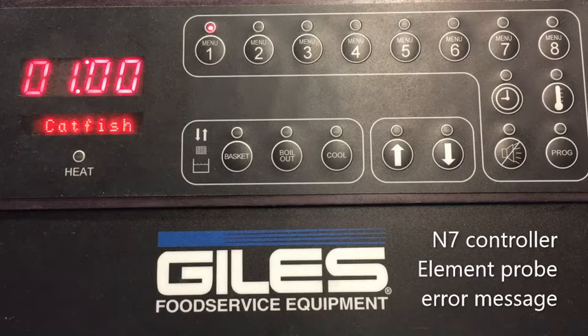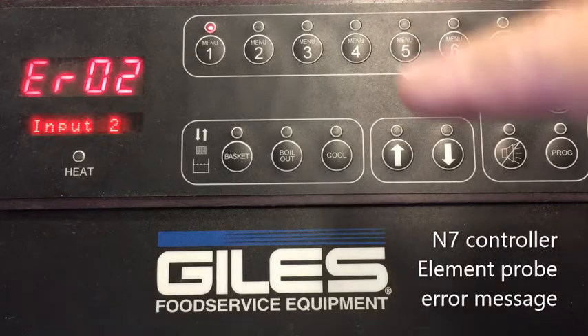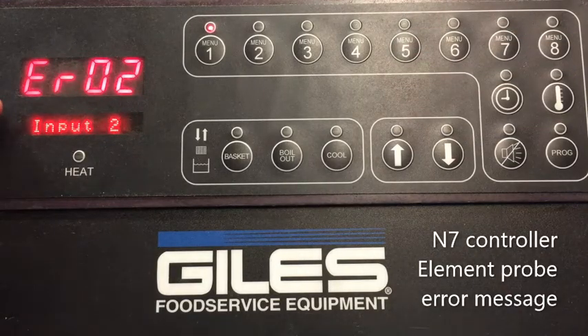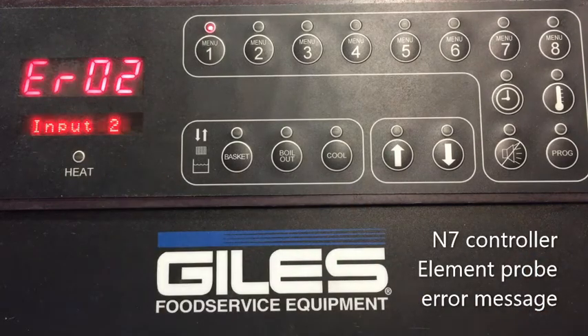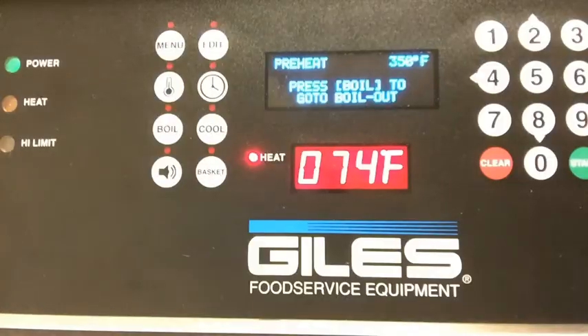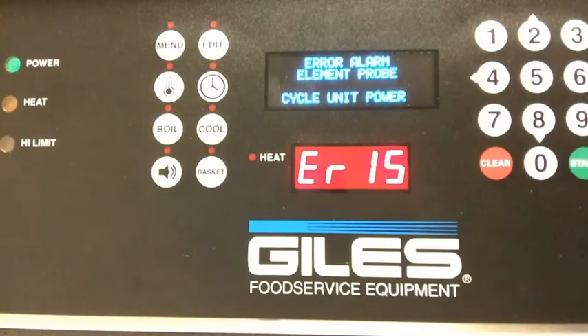Your element probe is of course the one on the left that is tied directly to the element. What you'll see is an error 2 message if it loses a connection. You'll notice now we got an error 2. We of course have no heat. With our element sensor, we would get an alarm, and that alarm would actually tell us what that is, and that we would have to go ahead and cycle.